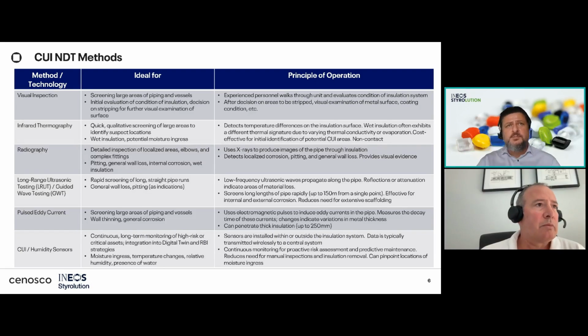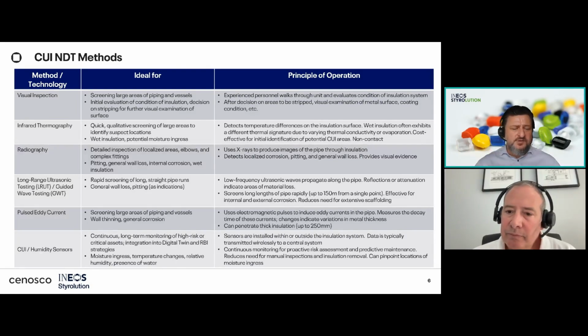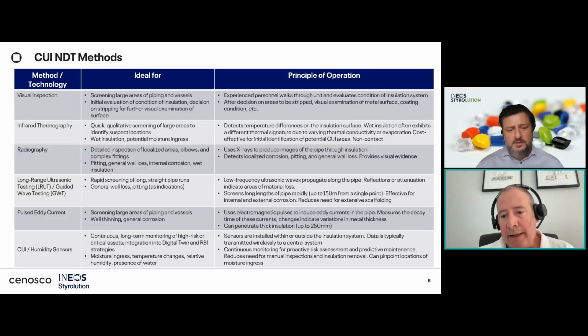So sometimes you want to reduce the cost and you want to reuse the cladding because the cladding is in good condition. You can add the few, let's say, missing pieces. In order to do so, you're more or less obliged to use the same type of insulation so that you end up with the same diameter, with the same dimensions. Otherwise, you need a new cladding, and that would probably add several hundred thousand or a couple of million on top. But that's the whole idea of having the team that discusses this kind of thing, right? Exactly.